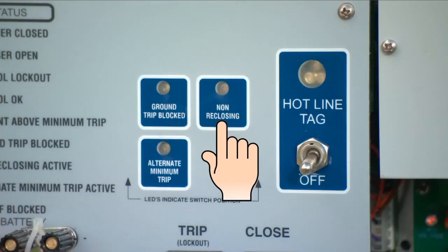Non-reclosing. By setting the operating mode switch to non-reclosing, the FXB control will block reclosing after an automatic trip, one trip operation to lockout, on TCC number 1 for phase and ground. When set in the normal reclosing mode, the FXB control will operate on its programmed operating sequence.